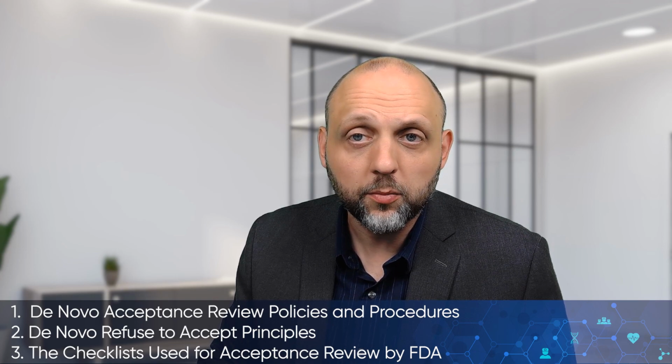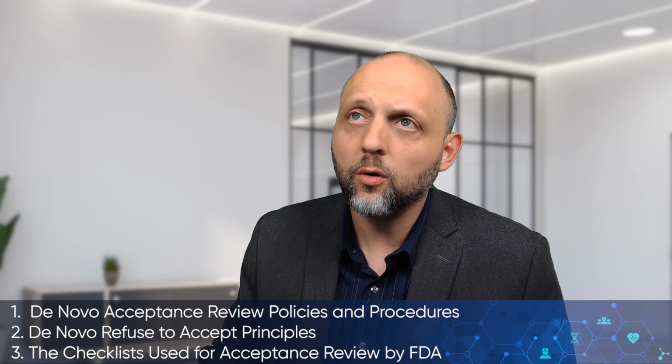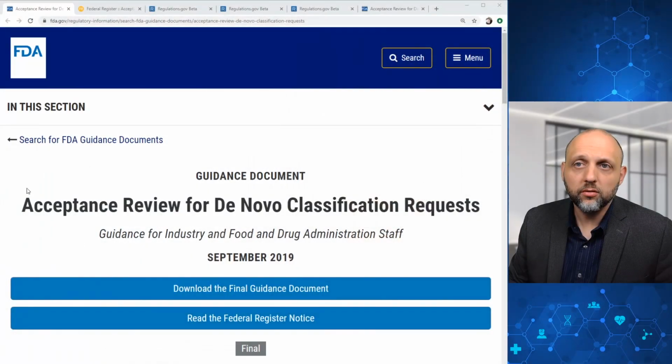I'm David Pudwill, and today we're going to be talking about FDA's guidance document on acceptance review for de novo classification requests published in September 2019. Three key takeaways from today's video are: 1, the de novo acceptance review policies and procedures; 2, de novo refuse to accept principles; and 3, the checklists used for acceptance review by FDA. So without much further ado, let's go ahead and get into the video.